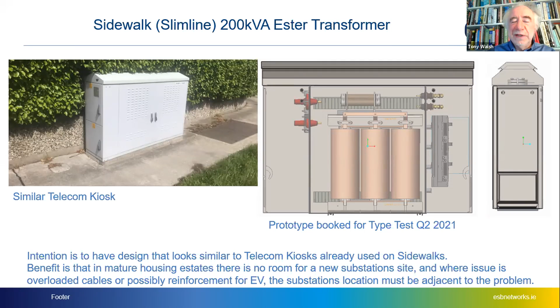I mentioned we doubled the loads on existing greenfield housing estates, and by designing for 5.5 kilowatts, what it means is we need to put in a bigger unit sub, we need 2 extra cables out of the unit sub, and if we do that, we have a 5.5 kilowatt average demand that each customer can take. The cables themselves reduce the voltage drop, but also reduce losses on the cables.